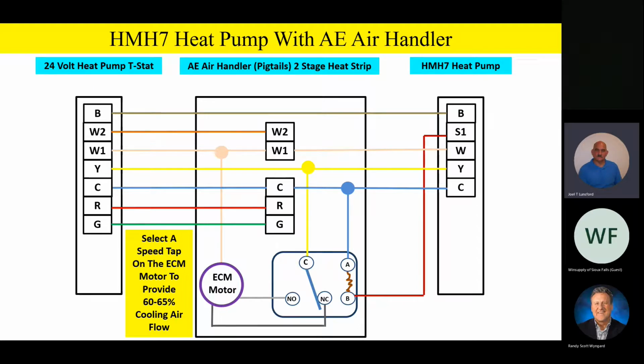So here's how all this works. The outdoor unit will modulate between 35 and 100% capacity. And what's going to happen is when it starts screwing down to around 60, 65% capacity, it's going to energize that S1 terminal outside and put 24 volts on that relay. Once it puts 24 volts on that relay, those contacts are going to switch. And we'll show you an animation of that in a little bit. Those contacts will switch and it'll drive the fan to about 60% airflow. So the whole purpose of that relay is to sit here and switch from high speed cooling airflow to low speed cooling airflow based on that S1 output from the outdoor unit when it's calling for reduced airflow because it's in a reduced capacity state.